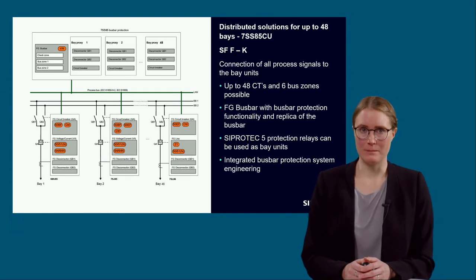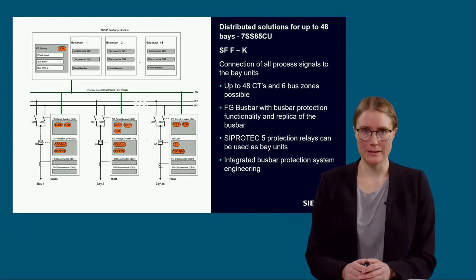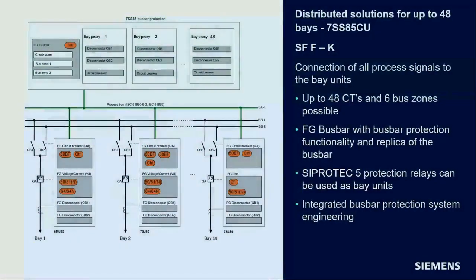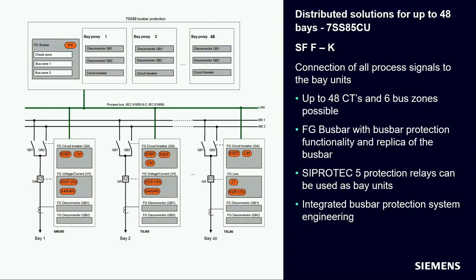With the 7SS85CU solution, a setup with up to 48 measuring points and 6 bus zones is possible. Also, in the 7SS85CU solution, every SIPROTEC 5 device can be used as a merging unit. The requirement to the device hardware of the 7SS85 is to have an Ethernet BD module for 16 measuring points each. With 3 modules, one comes then to 3 times 16 measuring points, which are altogether possible.